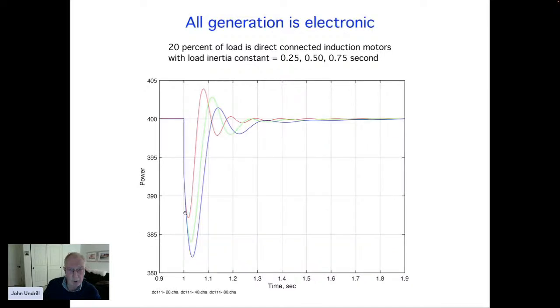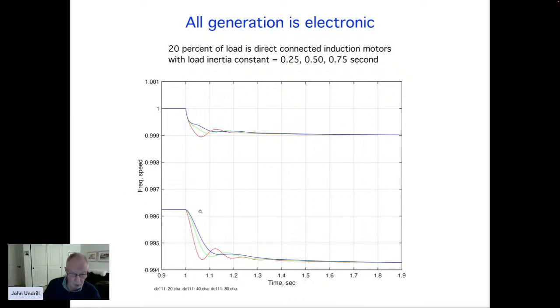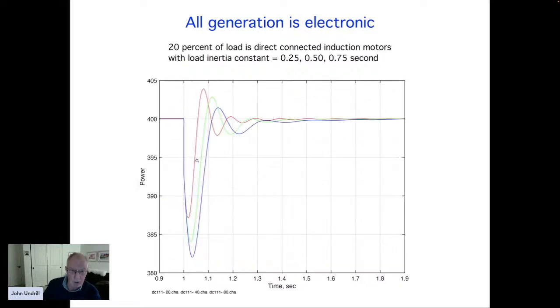Enough of that. I took the power developed by the electronic converters corresponding to this event, and you see that as the motor inertia is increased, the amount of power that is consumed transiently is quite significantly affected, but the settling point, according to the droop equation, is always the same.